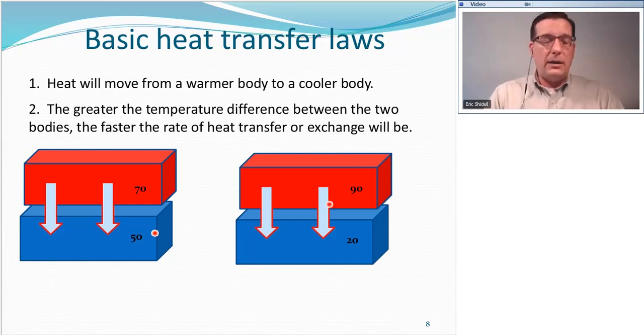And right now I want to lay a really important concept on you, and that is this concept of temperature difference. When we're measuring temperature, we always want to be measuring at least two temperatures. Simply knowing a temperature isn't very helpful unless we have something to compare it to. For example, if I know that the water coming out of the boiler is 180 degrees, well, that's good to know, but it's not nearly as valuable when I also know that the water coming into the boiler is 160 degrees, and more importantly, the difference between those two numbers is 20. The temperature difference is most important.